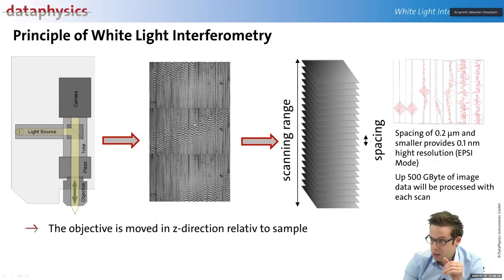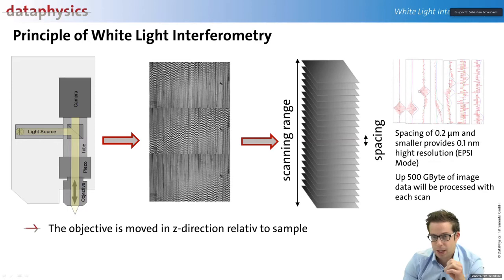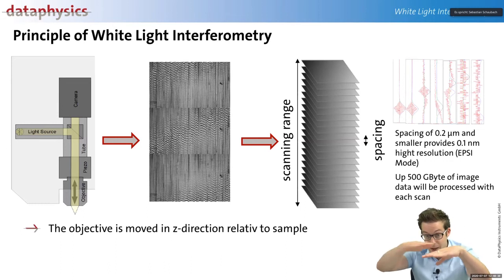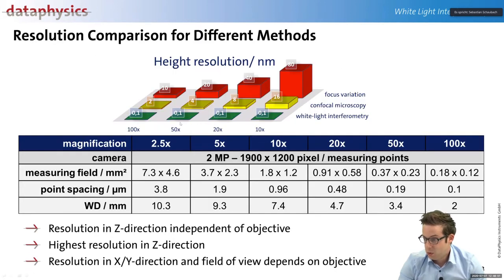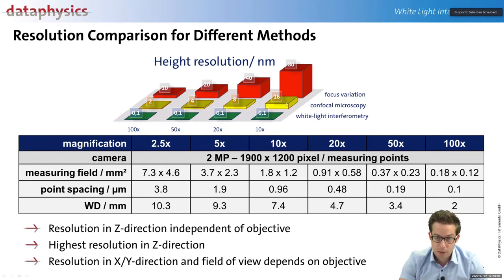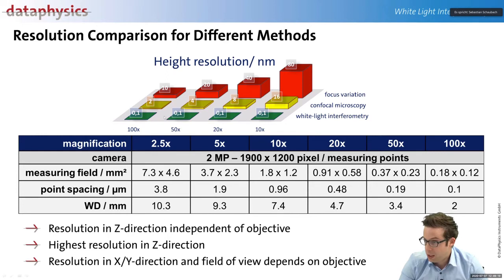We scan layer by layer and make an interference image on the surface at the same time. Compared to focus variation or confocal microscopy, where height resolution is typically in the higher nanometer range, we use white light interferometry — producing interferograms on the surface — which achieves extremely high resolution in the Z direction. Importantly, for all objectives you can use, the height resolution is always exactly the same.